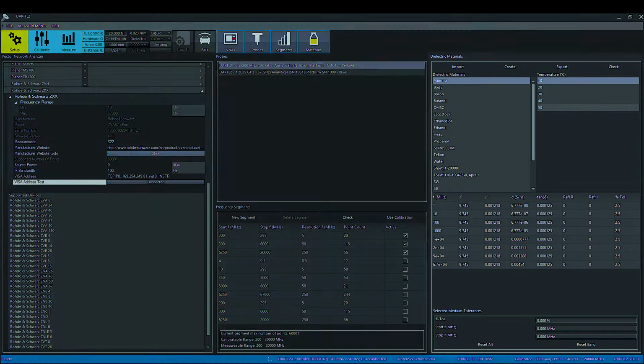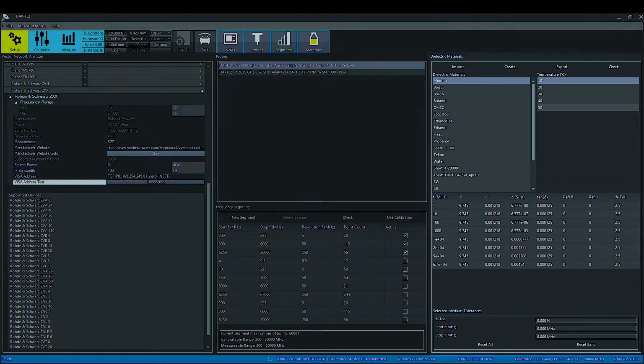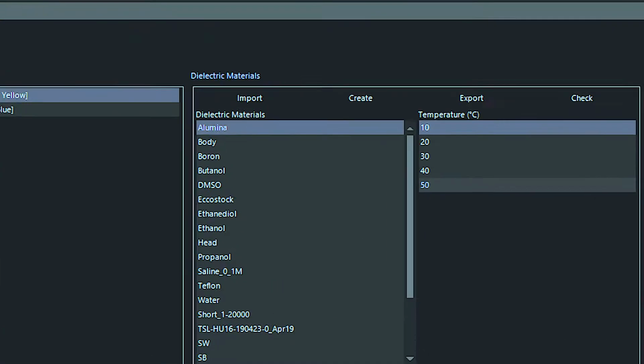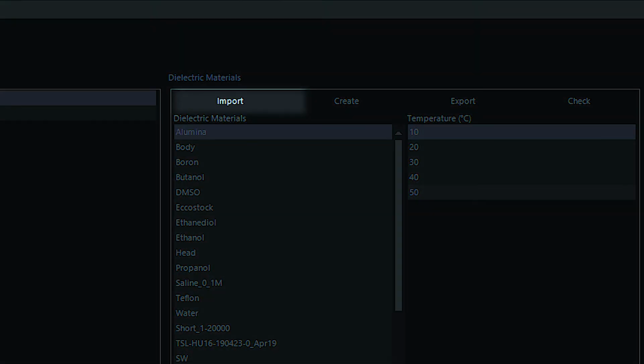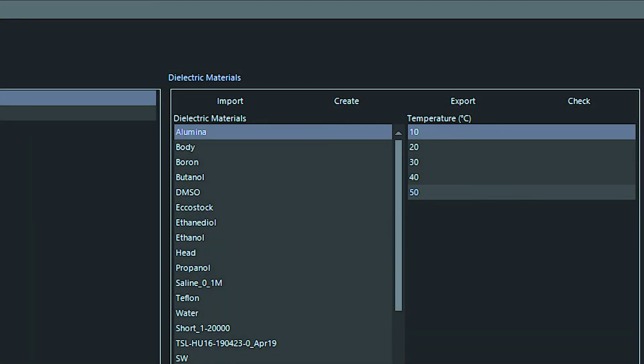Here on the right side of the DAQ software GUI, in the setup mode, you see the dielectric material section, which includes target data values for different reference materials. These data are used during load calibration and also to observe the deviation of measured data from target values during the measurements. It is possible to import any desired data simply by clicking on the Import button.